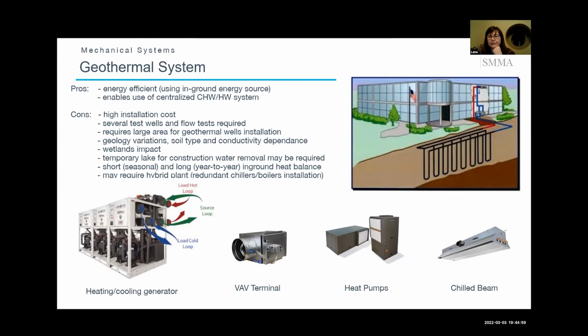Usually we drill for this particular project, the plan is for 500 feet deep wells. Two pipes are inside one bore, and then they are grouped into headers, and then they go back to the building. The building usually has either a heat exchanger or a generator that separates the groundwater from the building water.